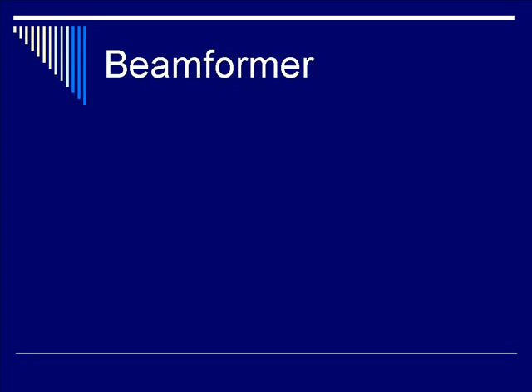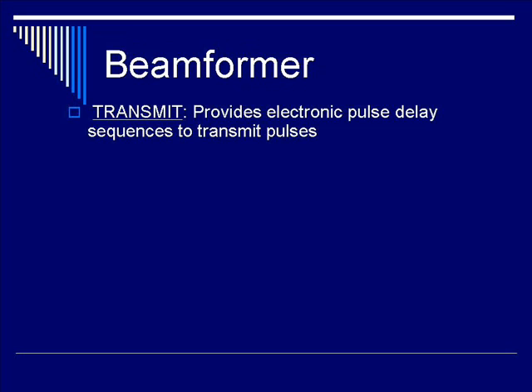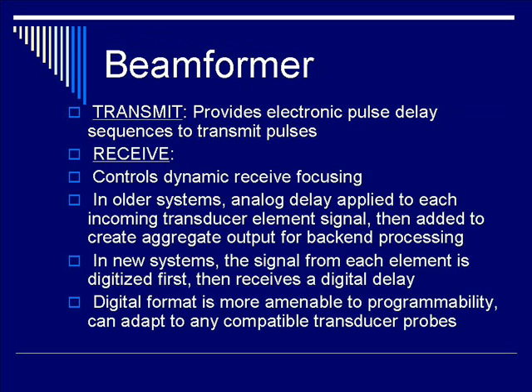Let's spend a little time talking about beamformers. What does it do? We know from previous discussion that beamformers are involved in transmission of the ultrasound pulse by providing electronic pulse delay to the high voltage pulser.